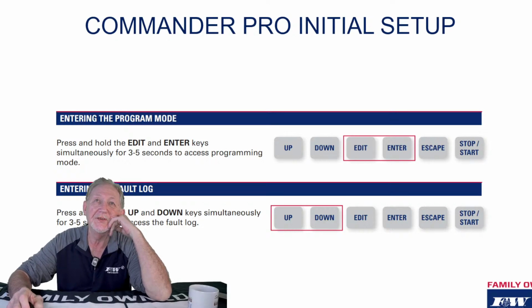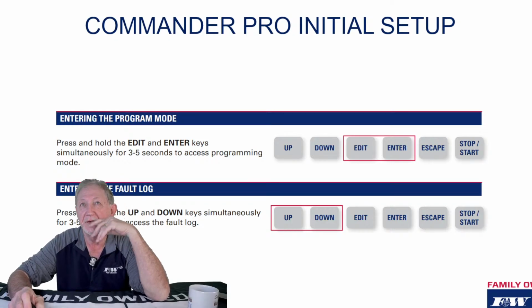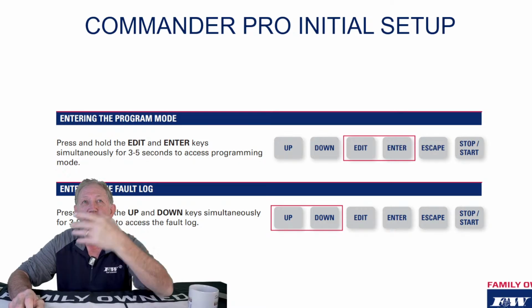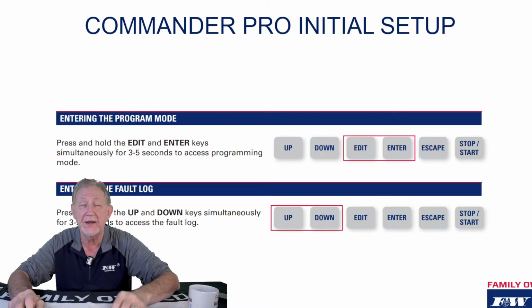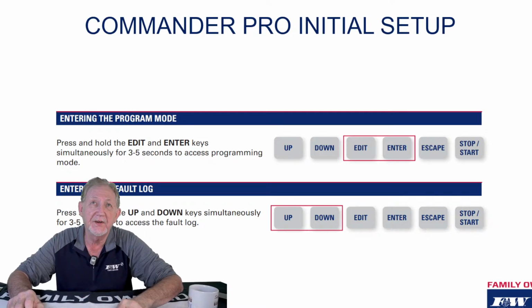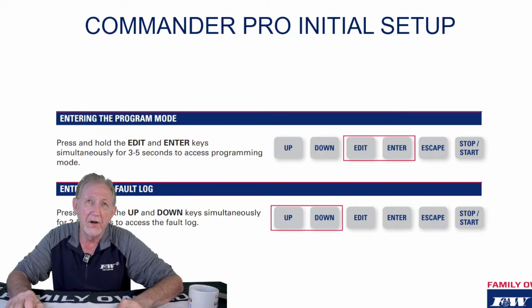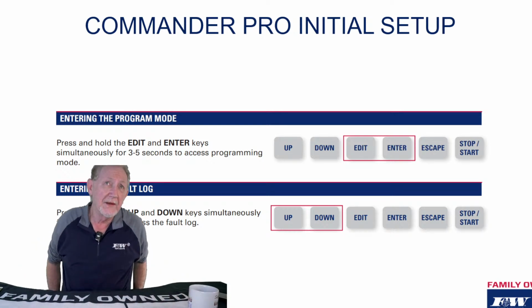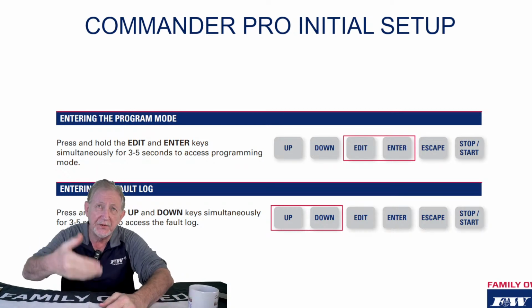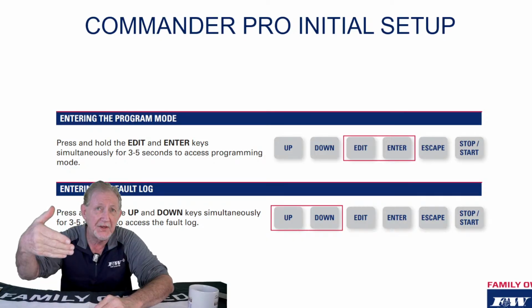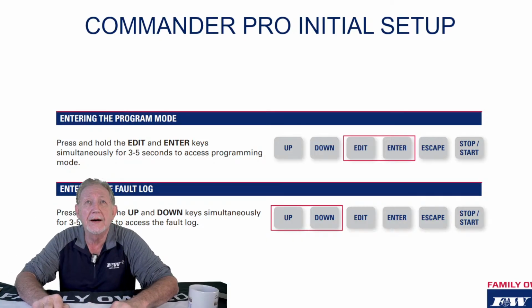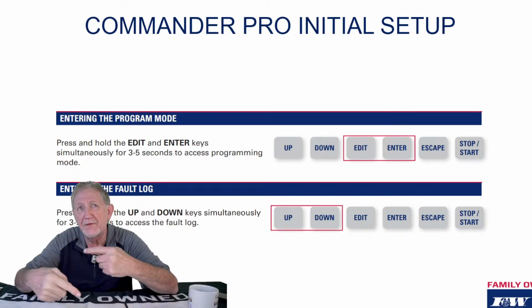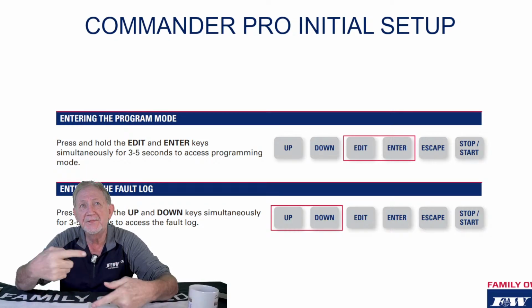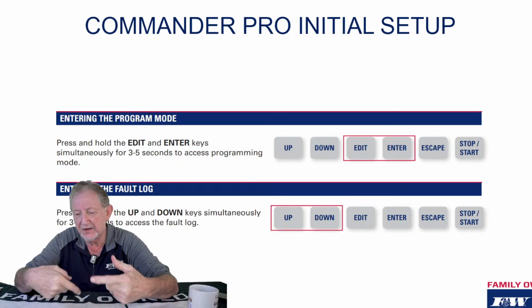The other two buttons that you can hold down simultaneously once you're in the drive is the up and down buttons. And what that up and down button is going to do is it's going to take you into a fault log. This particular drive, these TVS series drives, will store up to 20 faults. So you've got a history there of faults with a timestamp. And so it's a revolving fault log that we keep.